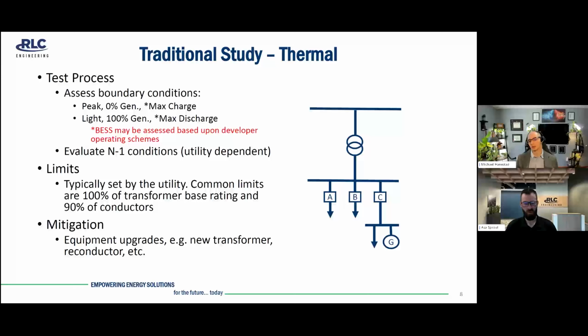You'll typically evaluate this on a substation level. So if we look at the simple graphic over here on the right, you can see that feeder C on the rightmost circuit has a generator. So from a substation perspective, we might look at loss of feeders A or B. We're reducing the load and increasing the export through that transformer. You can also evaluate this on a feeder specific level where you're losing some lateral load pocket that doesn't include generation, and you're increasing the amount of generation flowing through that circuit. For limits, it really depends upon the utility. Common limits we see are about 100% of transformer base rating or 90% of the conductors. And for mitigation, that's usually the equipment upgrade for where those violations occur.